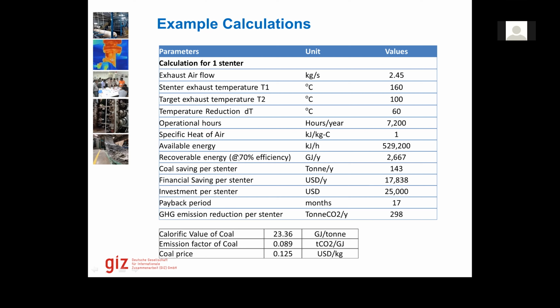We used that efficiency to calculate total recoverable energy, using the efficiency of the heat exchanger in this case to see how much we could recover. An air-to-air heat exchanger usually comes in with 70% efficiency. So we saw how much could be recovered and how much it would save in coal, considering the 75 to 80% efficiency of the oil heater, which is providing heat here.